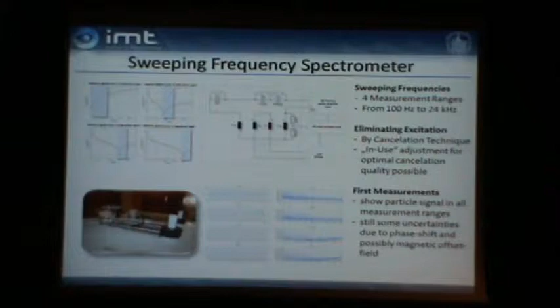Today, we already know, and we have heard this in many of the contributions at this conference, that sometimes we measure a signal in a zero-dimensional spectrometer, which looks fine, but the particle will not work on the MPI device. So this means that the particle reacts differently in different situations in the scanner, obviously, and we found out, and others did already, that the particles react differently on different trajectories. So here you see some fundamental trajectories that we produce in a new kind of spectrometer.